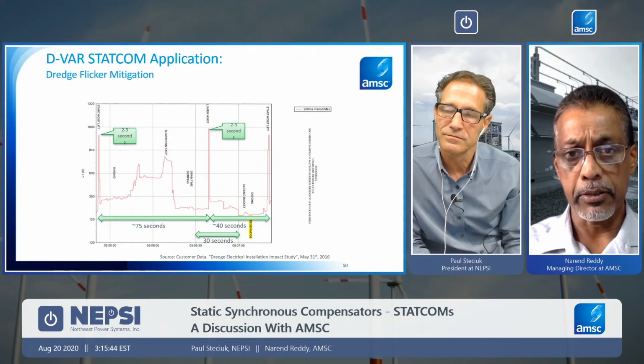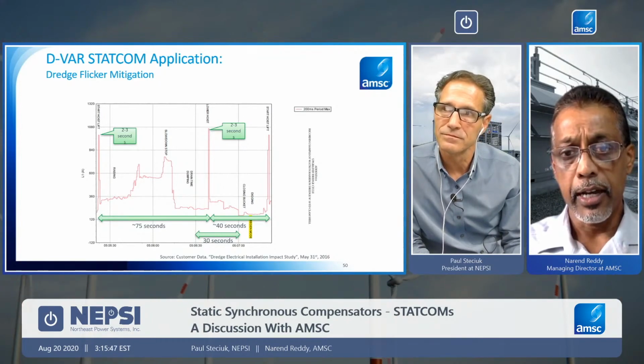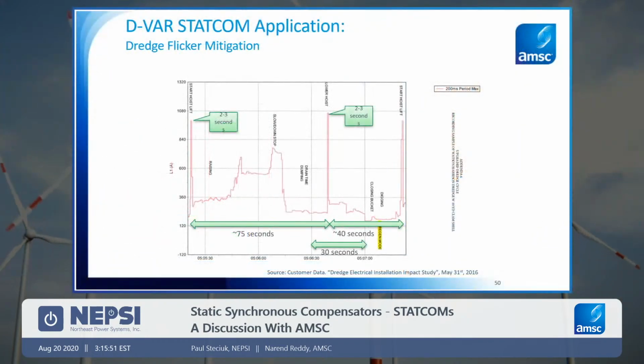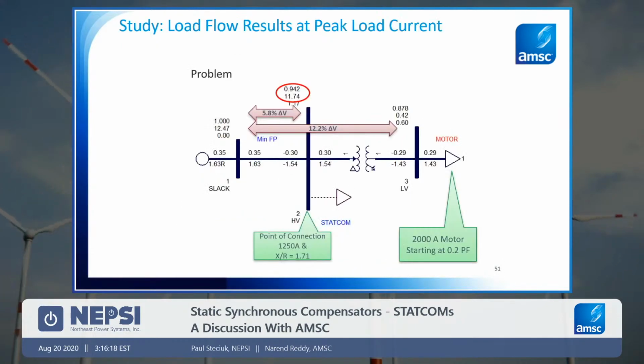A classic example that I'm going to talk about here is dredge flicker mitigation. As you can see in this graph, this is the operation of the hoist, and there's almost 2 kiloamps of current draw from the hoist motors that operate frequently, every time it's used. Not only when the hoist is operated, but also during the process time, there are a lot of variations in that load. When we studied this, we wanted to identify what the boundary-level voltage impact was, whether it was the impact to the grid or the impact on the factory, and the ability to help the facility make sure that it operates.